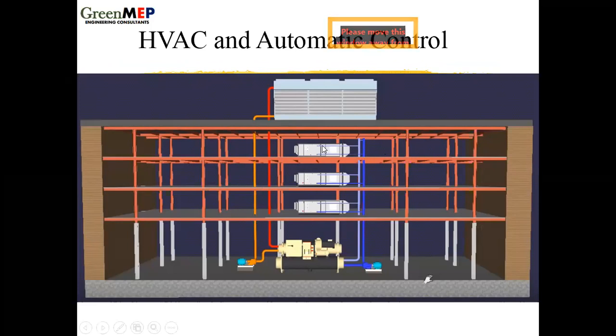Now, this chilled water goes through the cooling coils of the air handling units and then cools down the air. That means basically the heat in the air is absorbed into this water. It comes back. The chiller has to cool it down and send it back at a lower temperature. Okay. And the chiller is basically a refrigerator. It's a refrigerator that produces chilled water.